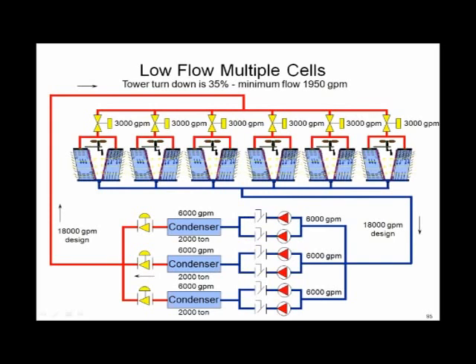Let's look at some common pitfalls. People seem to have fun looking at things like this. So let's look at low flow multiple cells. Remember dry air disease? Let's take a quick look. Here is a large process plant with 6 1,000-ton cooling towers on it, actually located physically in South Carolina. But remember, we said up until 90.1, cooling towers did not have any kind of minimum turn down requirement. So most towers would turn down, let's say in this case 35%. Remember, 90.1 2010 now states all cooling towers have to have a turn down to 50%.